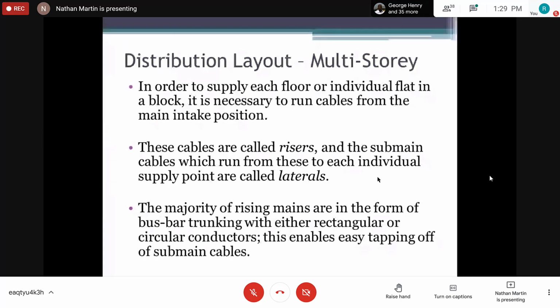All right, this is us elaborating on what to say about multi-story distribution, right? These cables are called risers, and the sub-main cables which run from the individual points are carried up by laterals, right? So the laterals basically distribute horizontally, while the risers distribute vertically. So when we go to the floor, then we have to distribute laterally or horizontally, and those are called laterals, right? The majority of riser mains are in the form of bus bar trunking with either rectangular or circular conductors, right? This enables easy tapping of the sub-main, right?